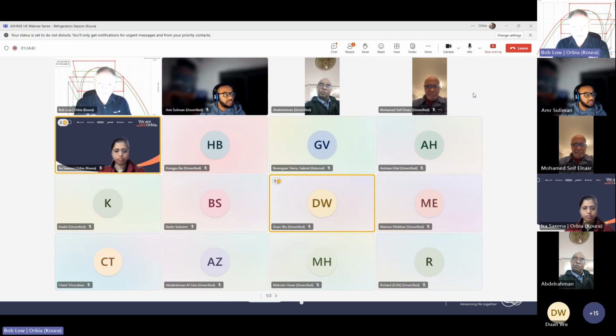The high CO2 content means the operating temperature limit is about minus 70 C cold space temperature. So it won't go all the way to minus 86 because the CO2 starts to drop out and become dry ice. But for a lot of the ultra low temperature market, fish freezing, for example, and fish transport, and for climate chambers, minus 70 C is good enough. We do have a variant of that blend in development, but we're not taking it forward just yet because we're waiting to see if the potential is large enough to justify the effort of commercializing it. But we know we can get colder by altering the CO2 content in the blend. Then it's a trade-off of GWP, flammability and desirability.